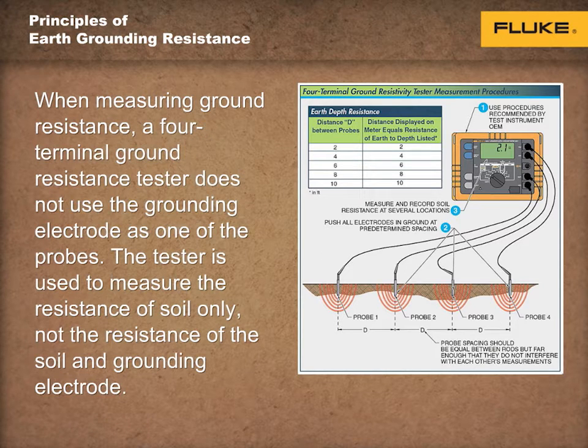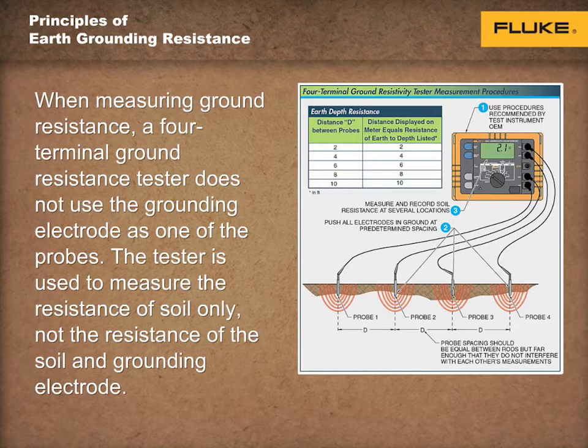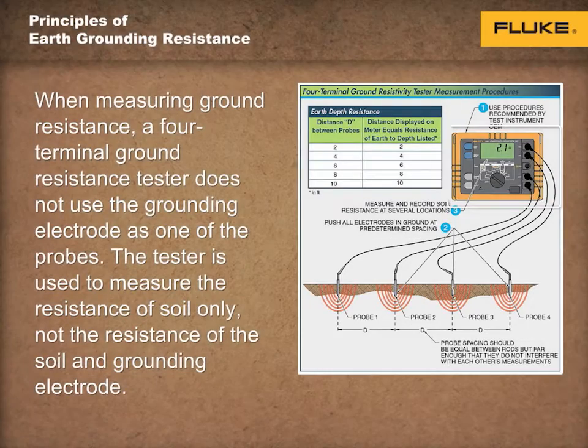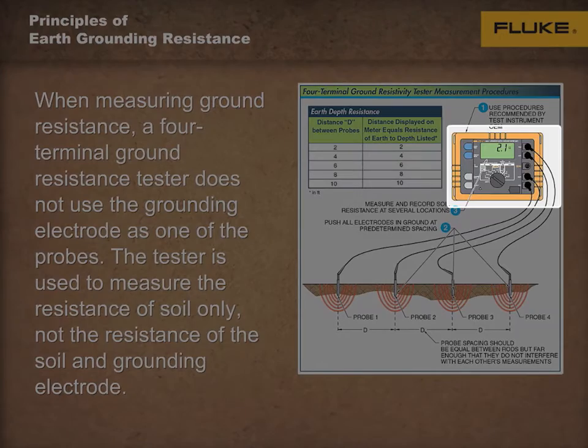A soil resistivity test is performed to determine the best type of grounding system to be used, which could include an electrode, a grid, a loop, or a plate. Testing the resistivity of soil requires a test instrument, such as a four-terminal ground resistance tester. The test instrument system involves four metal probes that are driven into the earth, connecting conductors long enough to connect the probes back to the meter, a tape measure, a calculator, and paper and pencils.